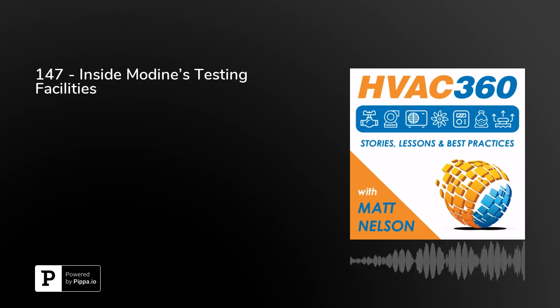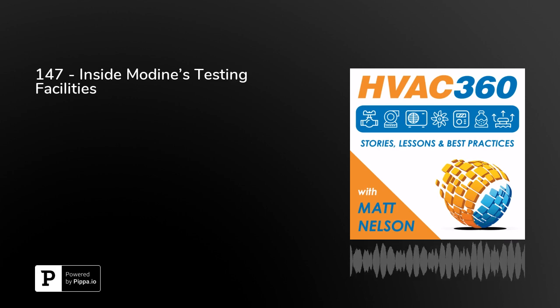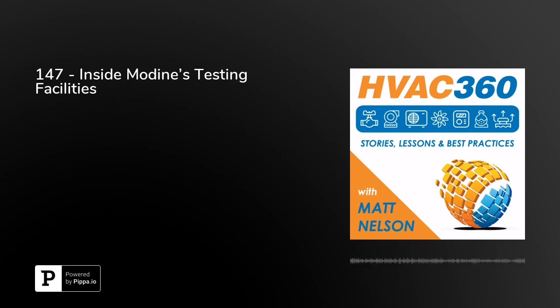If a customer is installing a unit, say in Yellowknife, and it's going to be seeing negative 40 degrees F, we can test for those conditions. How does a rooftop unit function at 125 degrees with a solar load on it? Those are things that we don't see even in third-party labs. Having the ability here to do that, plus even run at sometimes 24/7 for conditions, is a huge advantage to make sure that when our products go out the door to the customers, we've done everything in our power to figure out what conditions are going to be seen and to test those conditions to make sure the unit's going to perform like we expect it to.